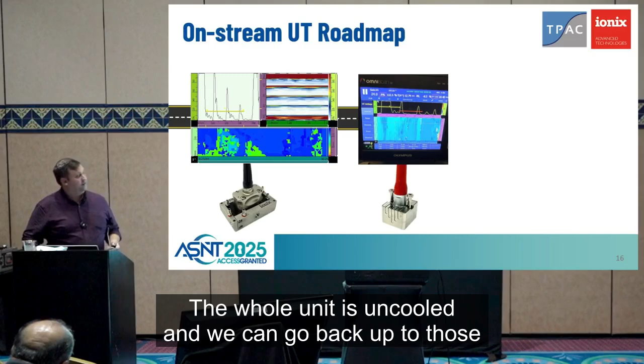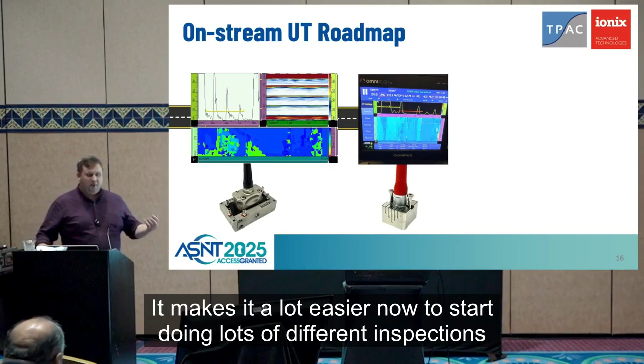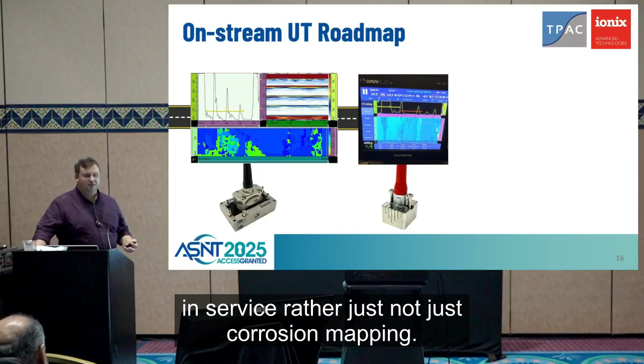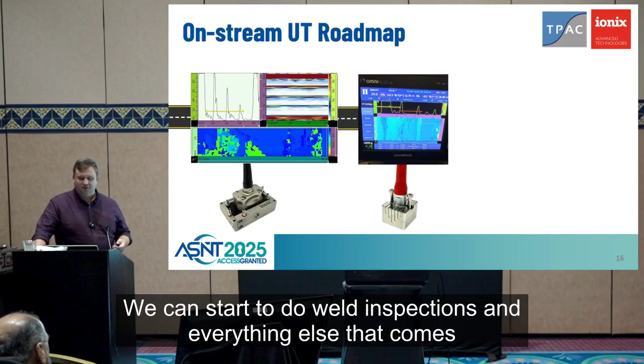But these then are sort of latest phase array - the whole unit is uncooled, and we can go back up to those temperatures, 670 Fahrenheit. So again, no duty cycling. It makes it a lot easier now to start doing lots of different inspections in service, not just corrosion mapping - we can start to do weld inspections and everything else that comes with the advantages of phase array.